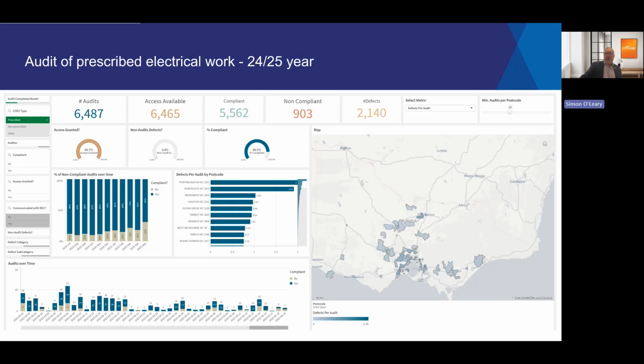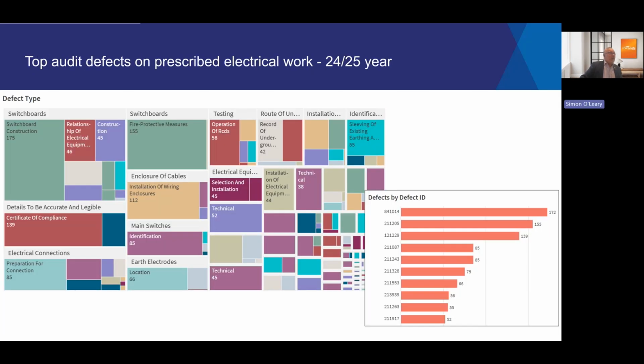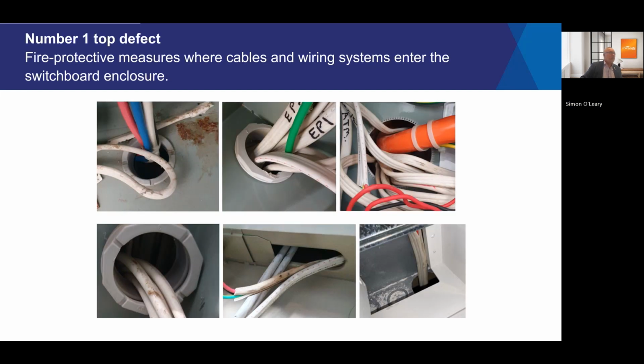However, there's still a number of defects in the system that we continue to see, and today I'm just going to speak on a few of the ones that we see at the top of the list. One of the most common defects we still see today is cable entries entering into switchboards. The wiring rules require that cables that enter into switchboards enter through close-fitting holes. And it goes on to say the close-fitting hole is a gap of no more than 5 millimeters. As you can see from these diagrams, the gaps around these cables are well in excess of the 5 millimeter requirement.